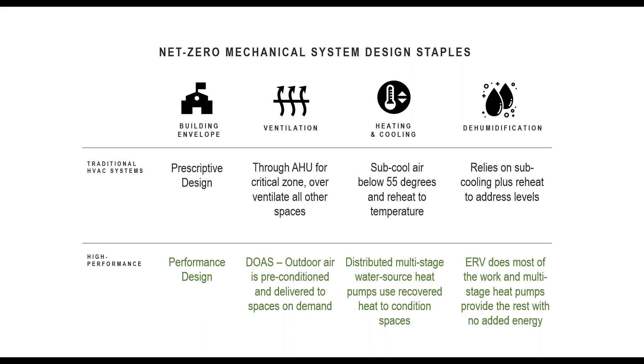Dehumidification, especially here on the East Coast, is a big deal. Some standard methods for dehumidification heavily rely on reheat. What we find is that the energy recovery ventilator in the DOAS unit is able to address the majority of that dehumidification and latent energy. The heat pumps throughout the space, typically 2-stage or variable speed compressors, are able to address any remaining latent energy without adding energy consumption.